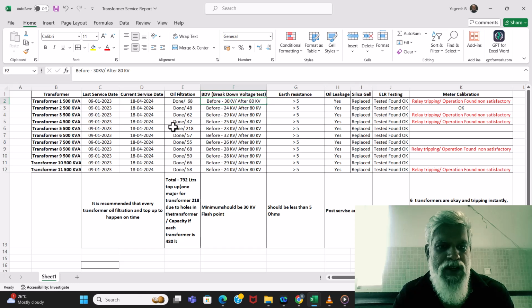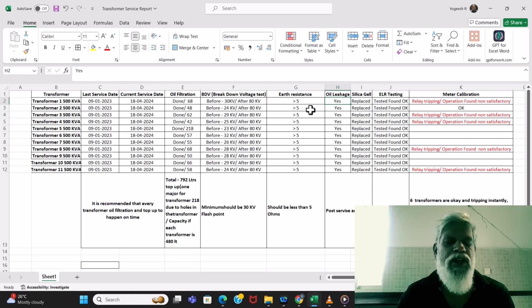So this part is taken care, oil filtration is taken care. The third point is earth resistance, which is measured in ohms, and it should be less than 5. So each of these transformer has a specific number, which will be published in the report, and you'll be able to see the exact number. However, all of them post this were within the range. Similarly, initially when we did the audit, there were oil leakages. We found about 4 to 6 oil leakages, and later on, while oil filtration, we found even more oil leakages. So we have arrested all the 11 transformers oil leakages.